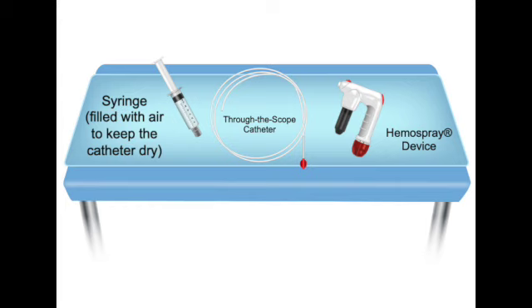Right. So once the tip is positioned correctly and they're sure it's dry, it gets connected, and the source says tightly connected to the main Hemospray device handle. And this handle needs power, a propellant. Yeah, the whole system is powered by an external cylinder of carbon dioxide, CO2. CO2. Why specifically CO2? They were just using air to flush the catheter. Why not just use compressed air to push the powder too?